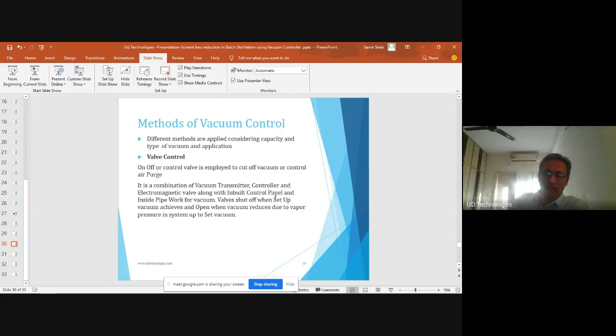So, what is vacuum control? Now I will come to the instrument philosophy. How will any control work? You need one sensor, a second controller, and a third, the part which is to be controlled. For example, if we are talking about temperature control with electrical heating, the temperature is heated by the electrical heater. What do you need in the temperature control circuit? One is the sensor, that is the temperature sensor. Second is the temperature controller, and third is the heater.